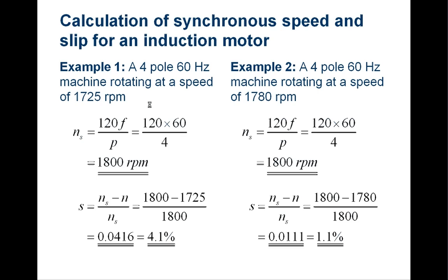Here is a demonstration calculation of synchronous speed and slip. For a four-pole 60 Hz machine rotating at 1725 RPM, the synchronous speed is NS = 120 × 60 / 4 = 1800 RPM.